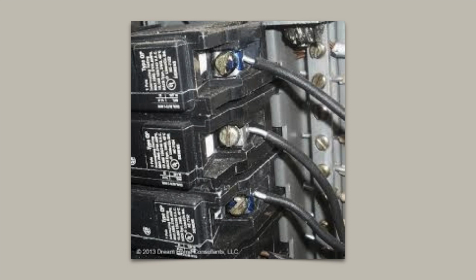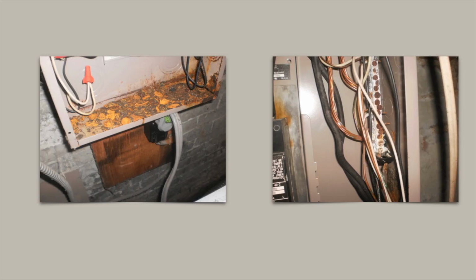Aluminum wiring can be safely used if the breaker and the outlet or switches are rated for aluminum wiring use. Breakers are marked for this rating for aluminum, but it is not possible to determine if outlets are so rated. When you see aluminum branch wiring in the panel, write it up as a defect.